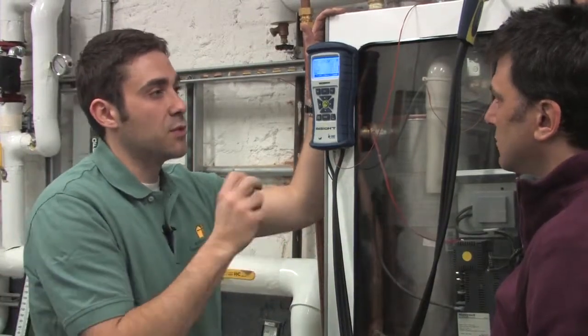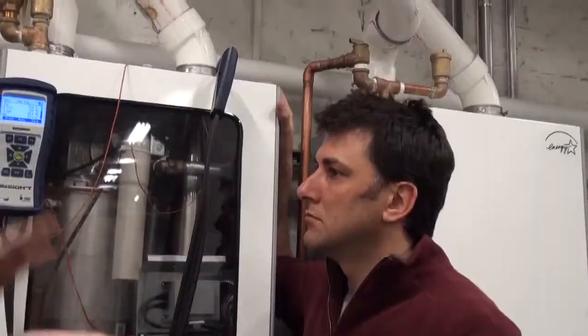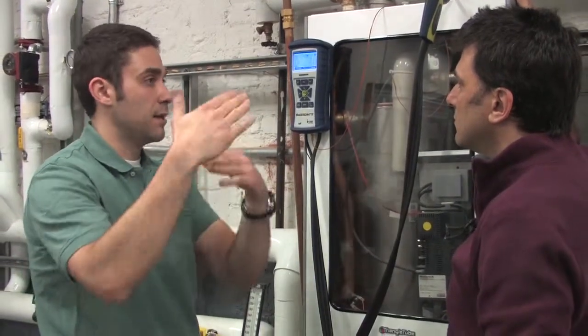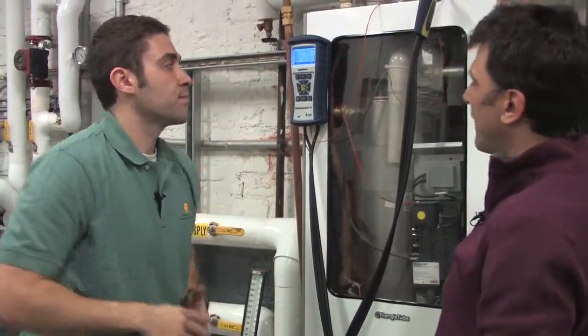The gas pressure is set a little too high on this one. And then that air to fuel mixture is off a little bit. We're getting the carbon monoxide production. That's why we see a higher CO2 than we would want, and we see a higher CO and a lower excess air. So you really are fine-tuning these systems, even with something as brand new as this.